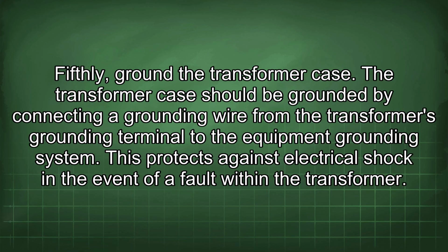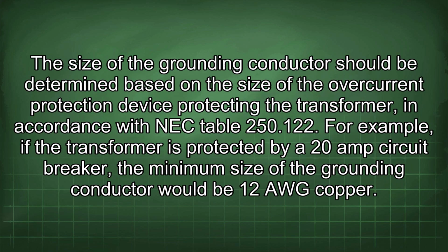Fifthly, ground the transformer case. The transformer case should be grounded by connecting a grounding wire from the transformer's grounding terminal to the equipment grounding system. This protects against electrical shock in the event of a fault within the transformer. The size of the grounding conductor should be determined based on the size of the overcurrent protection device protecting the transformer, in accordance with NEC Table 250.122. For example, if the transformer is protected by a 20 amp circuit breaker, the minimum size of the grounding conductor would be 12 AWG copper.